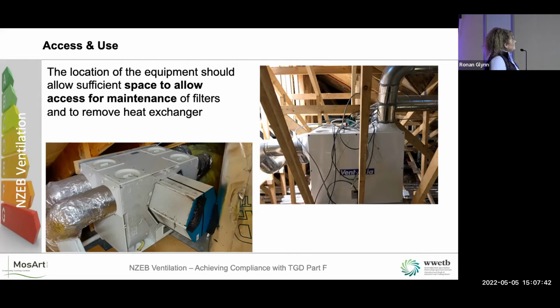So if you have dirty filters, the dirt will end up going in on the heat exchanger. So every now and again, about every 2 years or so, you have to take out the heat exchanger and give it a clean. So as you can see here, it's blocked. So you can't take that heat exchanger out, and you can already see that there's mold building up on the heat exchanger. So what you don't want now is to be supplying that into your bedrooms and inhaling it at nighttime. So we're saying there, that's not great either.